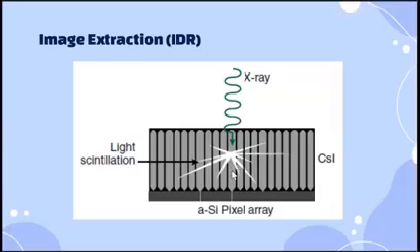So, okay, let me explain. Once X-rays interact with the scintillator, since it scintillates, it will produce light. Okay, so some of the crystals used for scintillators are cesium iodide and gadolinium oxysulfide. Okay, and they are created in a crystalline form in a vertical orientation. Okay, so in order for the light to be channeled directly towards the amorphous silicon or the TFT detectors, okay?